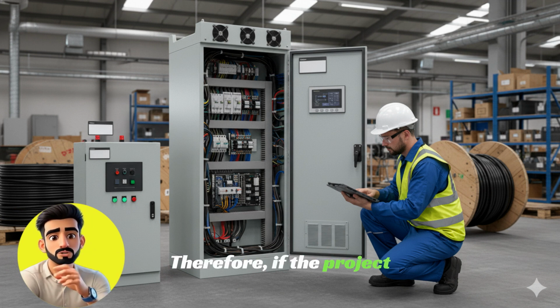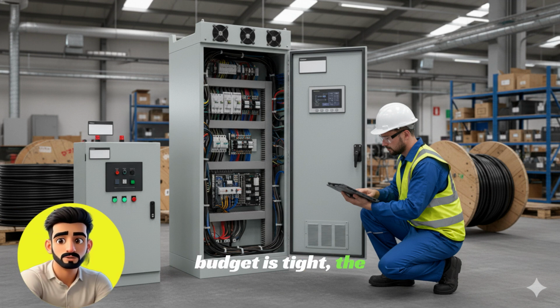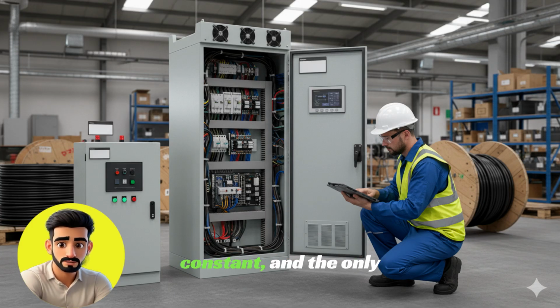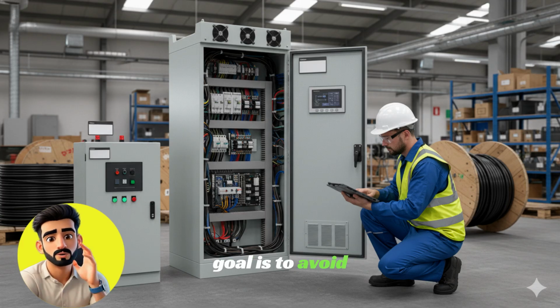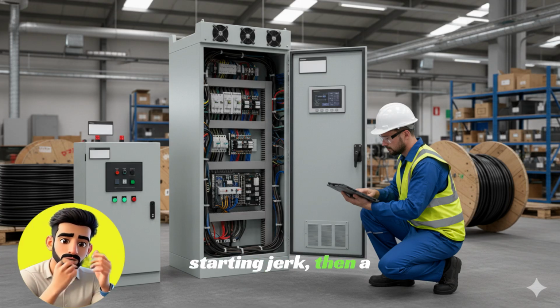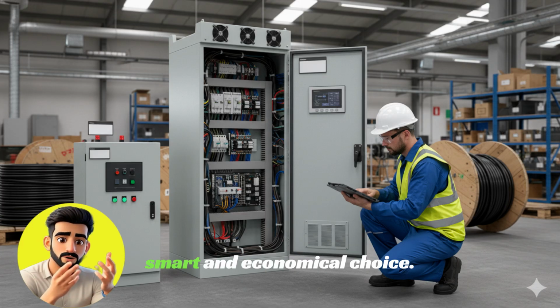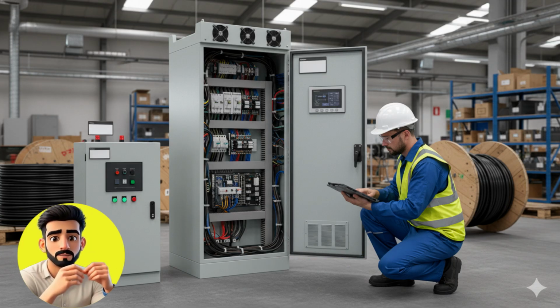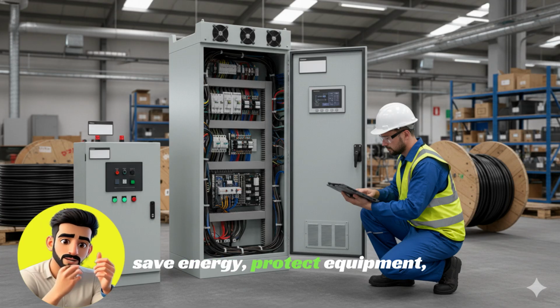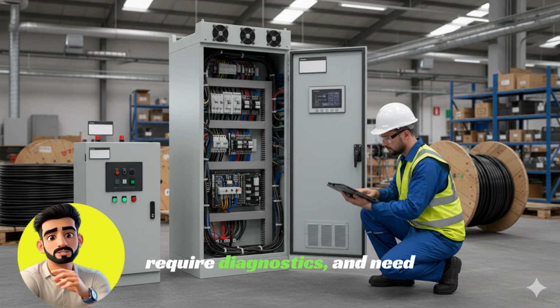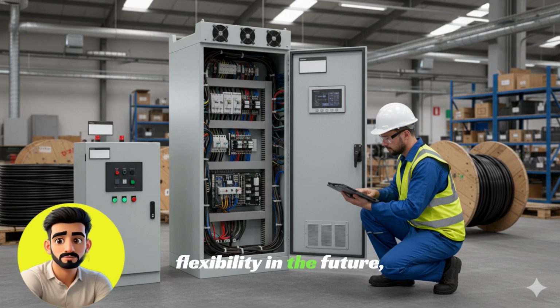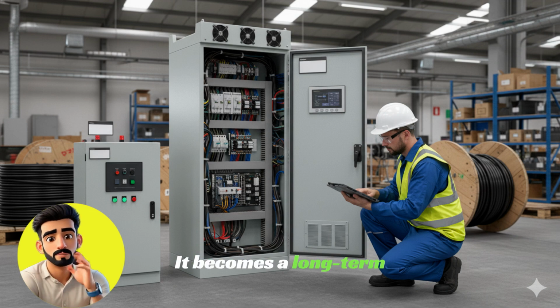Therefore, if the project budget is tight, the load is simple, the speed will always remain constant, and the only goal is to avoid starting jerk, then a soft starter is a smart and economical choice. But if you want to optimize the process, save energy, protect equipment, require diagnostics, and need flexibility in the future, then the additional cost of VSD is not an expense. It becomes a long-term investment.